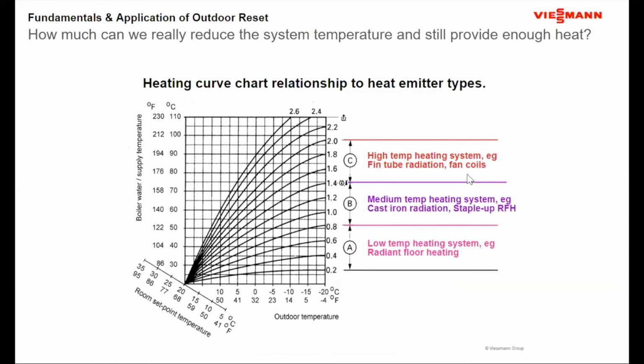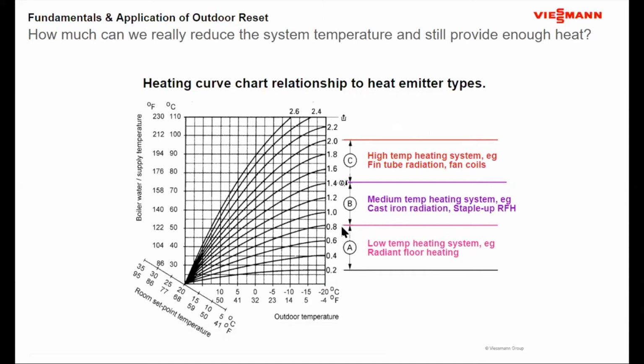Now, a lot of times from an aspect of setting it up, questions always come up about what the water temperature, what the heating curve needs to be. And typically somebody will say, well, if it's low temperature, it's probably going to be somewhere in here, maybe up to about a 0.8. Medium, maybe up to a 1.4. High temperature, fin tube radiation or fan coils, maybe a 1.4 to maybe a 2.0.